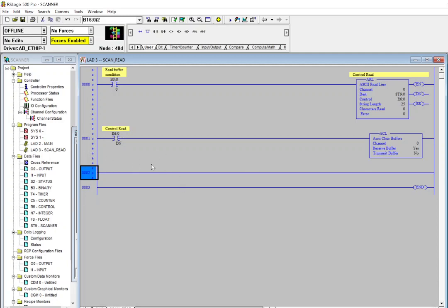So you will need a destination. For all of these data files, you will need to make a download to apply the changes. You cannot change the size, or add a data type, when the PLC is running or in program. You need to do a download. So I recommend you download or upload a backup of the program, and with the backup make the modifications, so you won't modify the current values in the PLC, and then make a download.